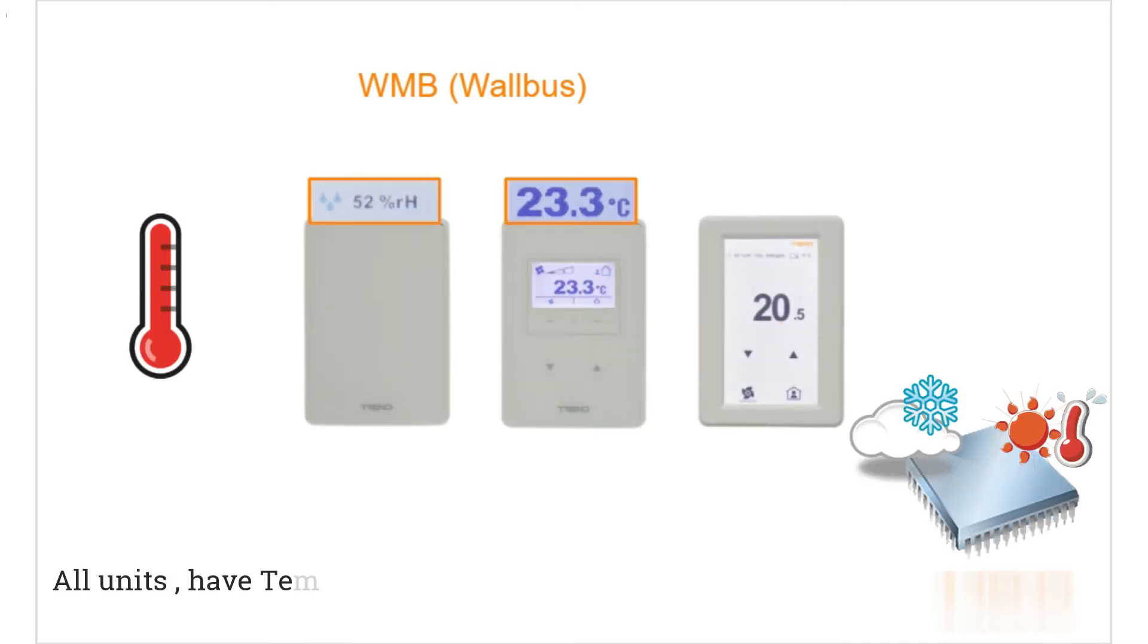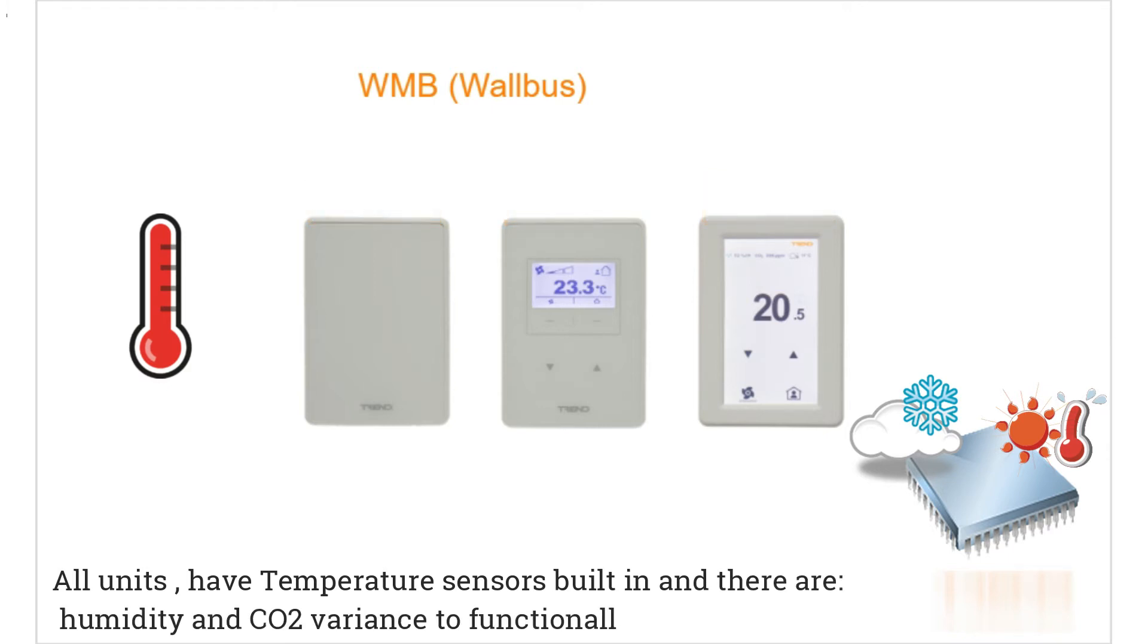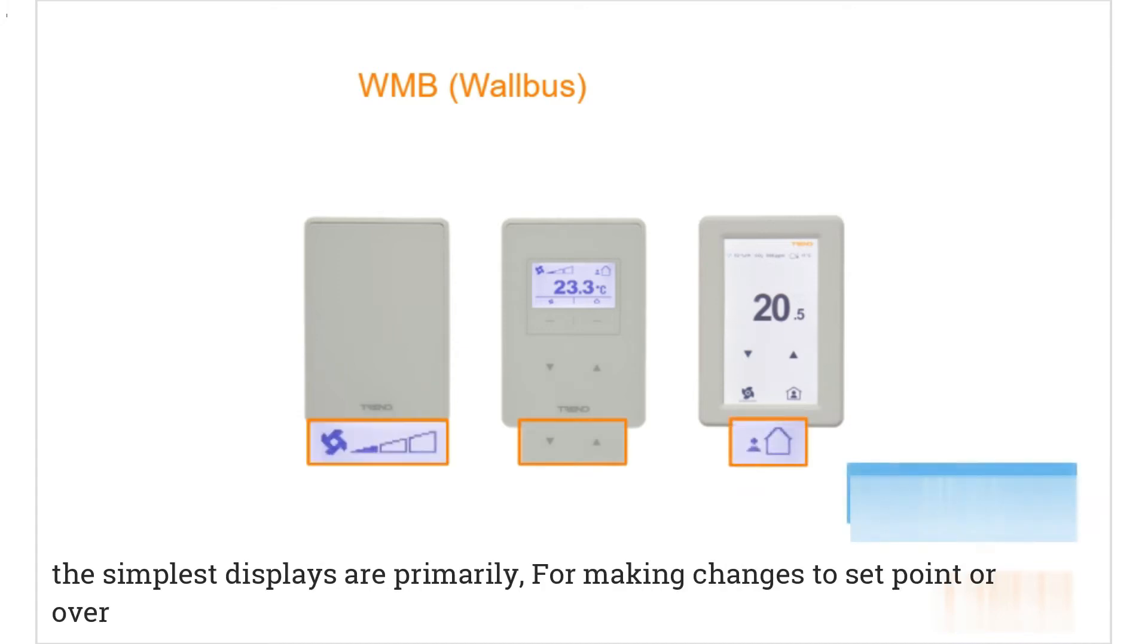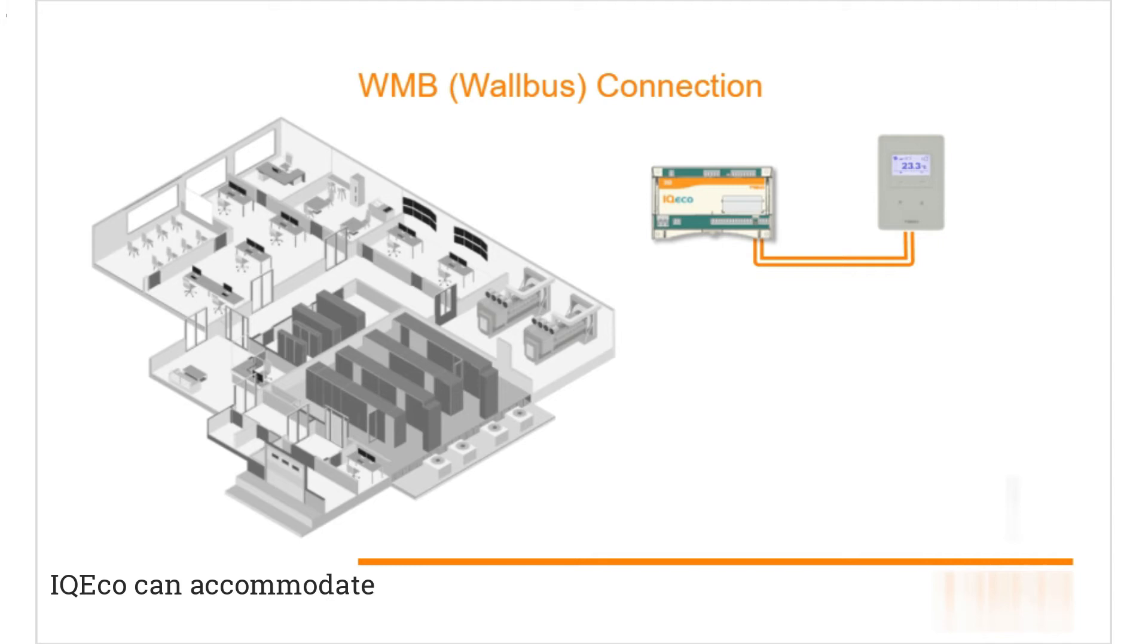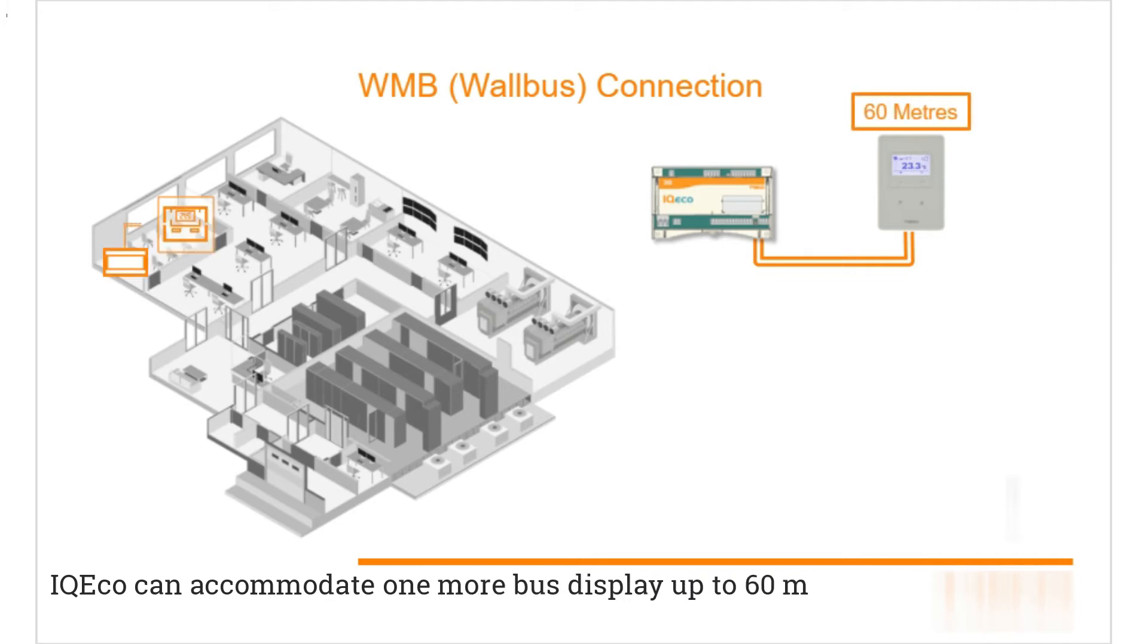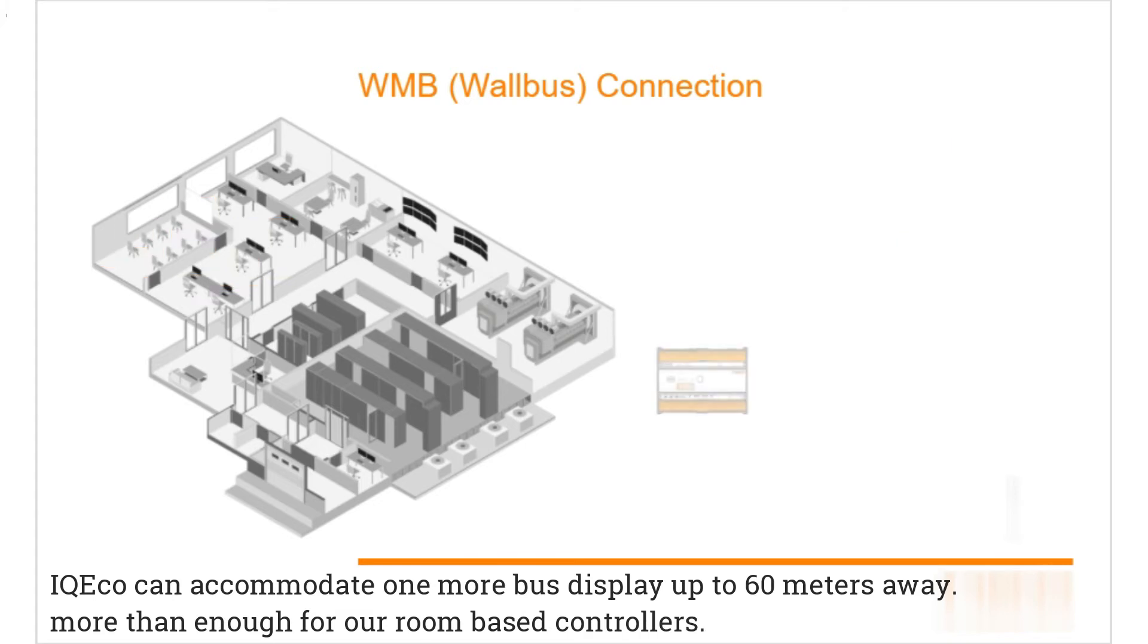All units have temperature sensors built in and there are humidity and CO2 variants. Functionally, these are the simplest displays, primarily for making changes to set points or overriding occupational or fan speeds. IQEco can accommodate one WMB display up to 60 meters away, which is more than enough for our room based controllers.